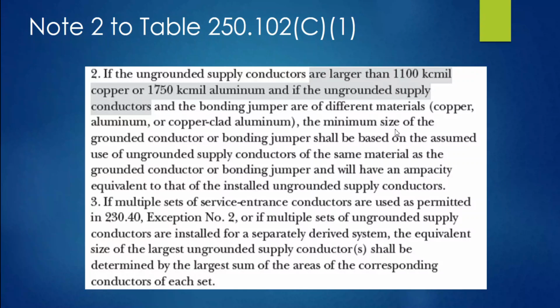Just to reiterate, the minimum size of the grounded conductor or the bonding jumper. So the minimum size, if you have differing materials, the size of those jumpers shall be based on the assumed use of an ungrounded supply conductor of the same material as the grounded conductor or the bonding jumper. Okay. So if I have aluminum conductors and I have a copper main bonding jumper, then I'm going to size this main bonding jumper based on the ampacity of whatever the size would be that's equivalent to whatever the aluminum conductors were, in the copper equivalent. Okay, that's a lot of words, but again, just bringing you to note 2 that states that. And again, one last time for all of you, this only applies when you're dealing with larger than 1100 kcmil.